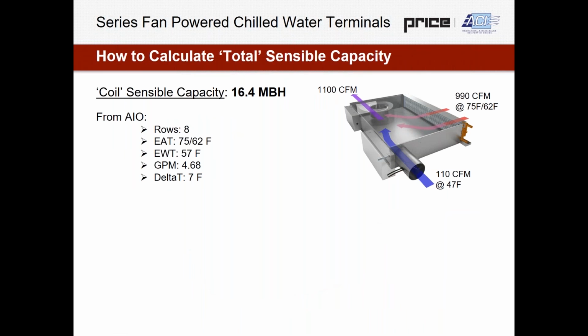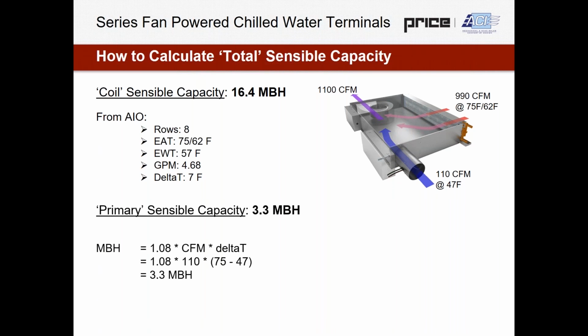So how would we actually recommend to calculate sensible capacity? Well, what we'd really like to look at is a coil sensible capacity being called out, as well as a primary sensible capacity being called out, and then a total sensible capacity being called out as well. The combination of these together is going to lead to the most understanding on the schedule. It's going to simplify it as much as possible, and it's going to make it very clear, just to make sure that people don't provide undersized or oversized equipment.